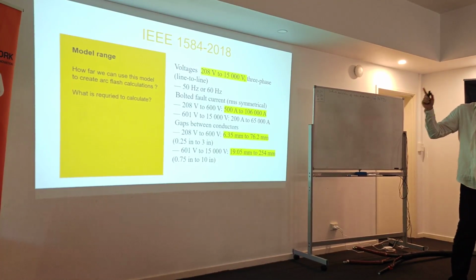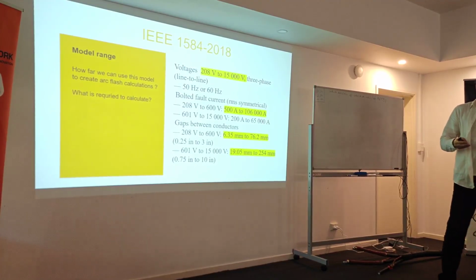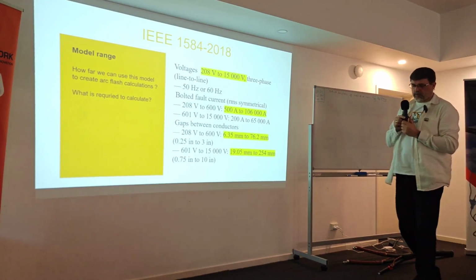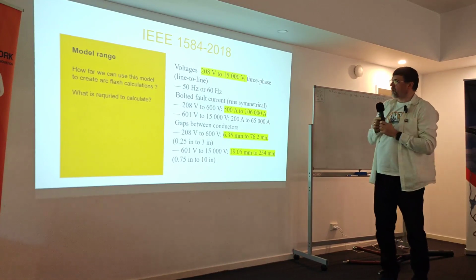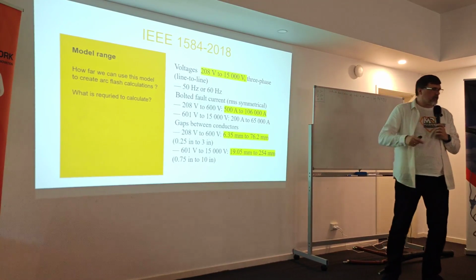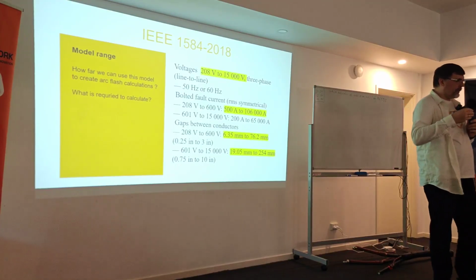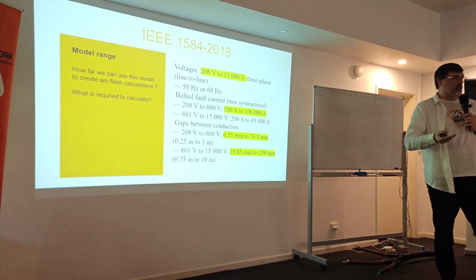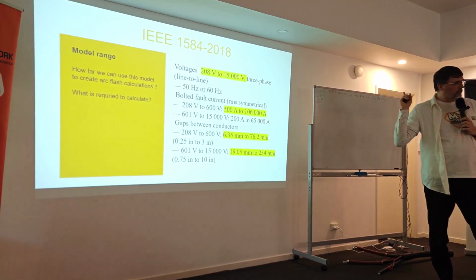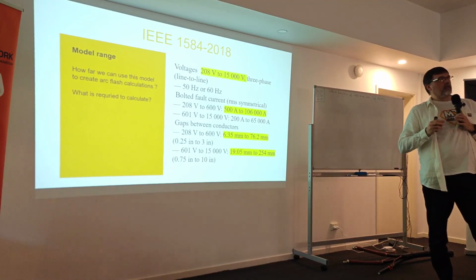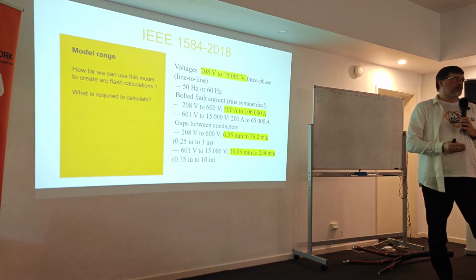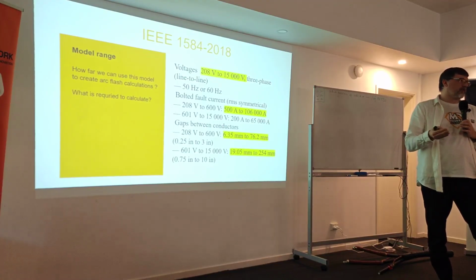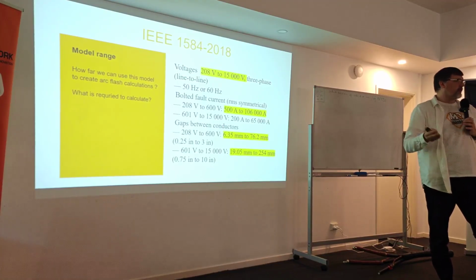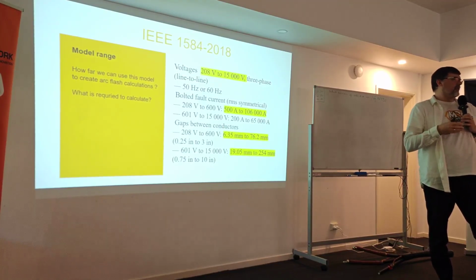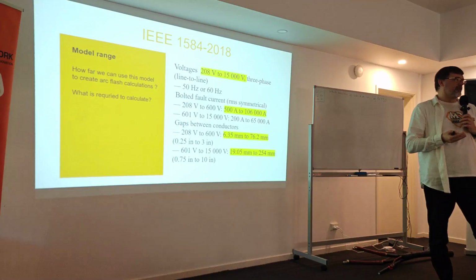So for calculation, we will use most of the time IEEE 1584. IEEE 1584 is a basic standard for calculation, but it has some limitations. And it's good to know them, because if you use software, at some point the software will tell you it's out of range or something like this, but if you do it by hand, you can just calculate, yeah? Nothing will stop you.